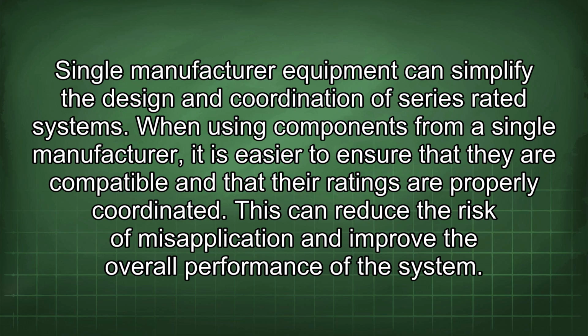Single manufacturer equipment can simplify the design and coordination of series-rated systems. When using components from a single manufacturer, it is easier to ensure that they are compatible and that their ratings are properly coordinated. This can reduce the risk of misapplication and improve the overall performance of the system.